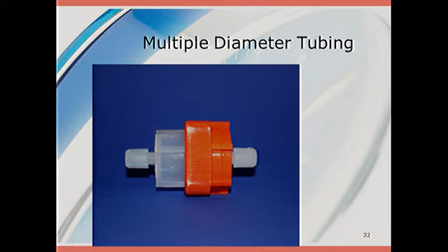But what we noticed was, because they're so large, that it's actually, well, let me go through this first. We've had to change our Excel spreadsheet because now we no longer have one line diameter coming into our site, from the manifold to the back of the analyzer. So we've had to change it to allow for a multiple diameter requirement. And how we've done this is, with this being the new filter holder, we've increased the length of your line by this much. That's how much change is made in this residence time.